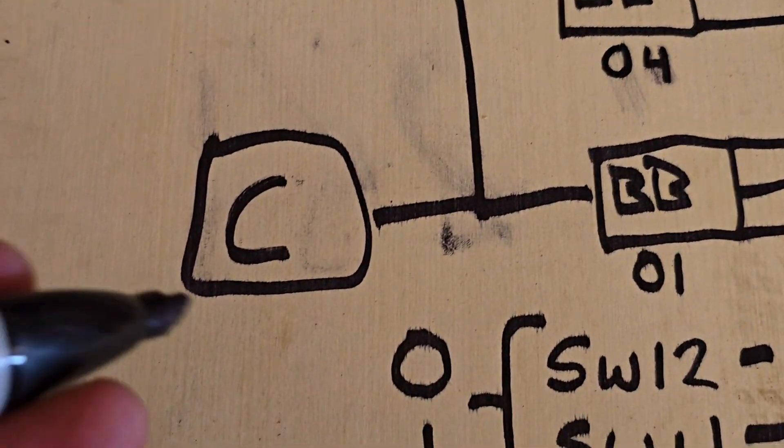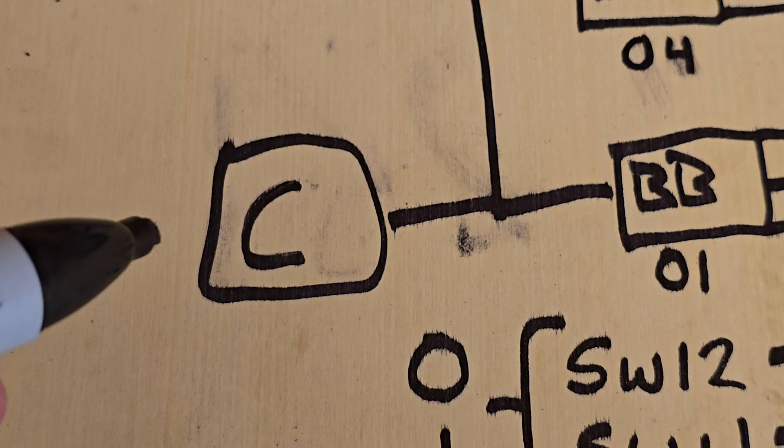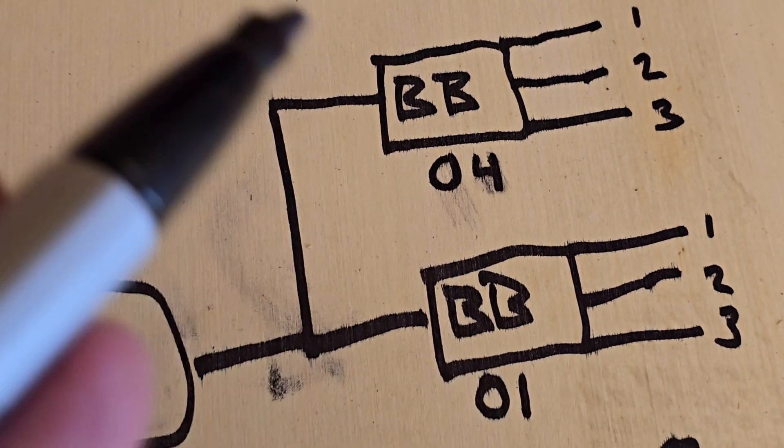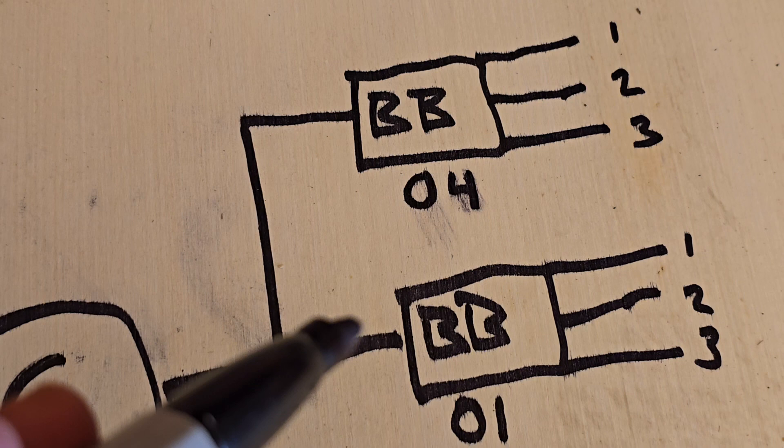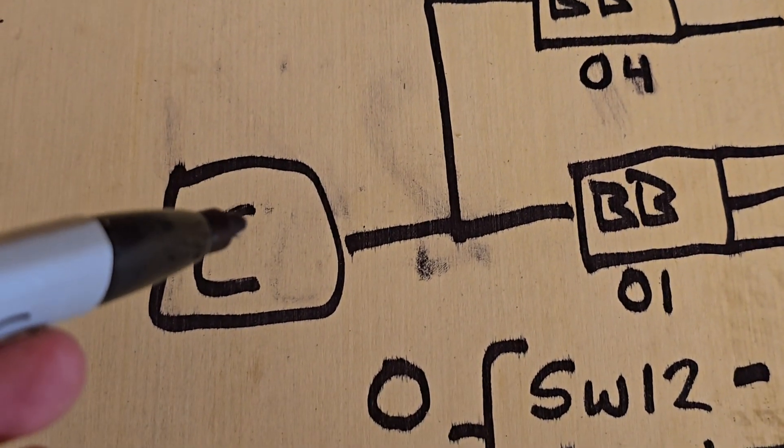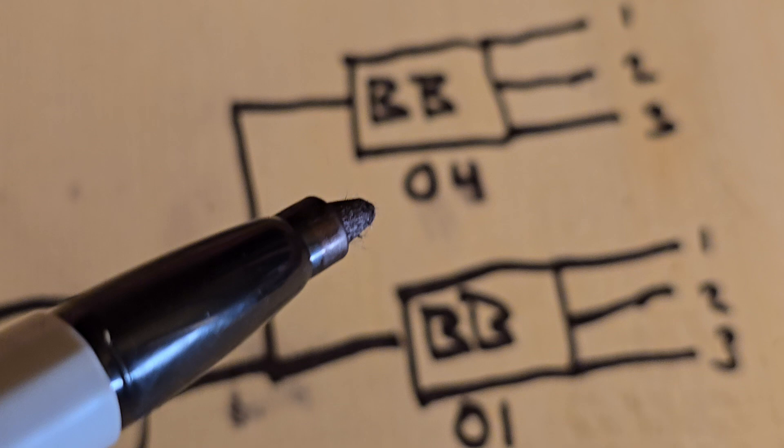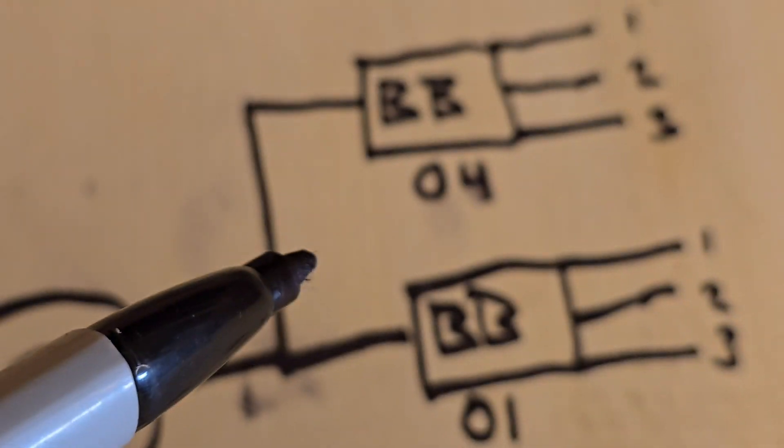Now there's some rotary dials out on your compressor side. It doesn't matter how you have these set up, this one is always going to start at 51. You can have up to 50 indoor units connected – that's rather unrealistic.